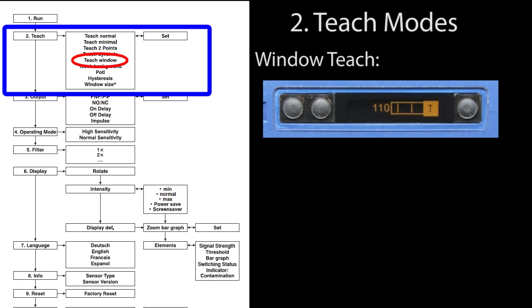In window teach, you put the object in front of the sensor and hit T1. If I move the object out of the way, you see two lines. Any object that passes between those two levels or within that window of values will be detected. Let's go back to run. If an object is too far away it won't be detected, and if it is too close it won't be detected. Only objects within the window will be detected.